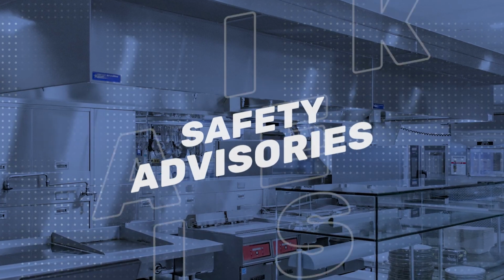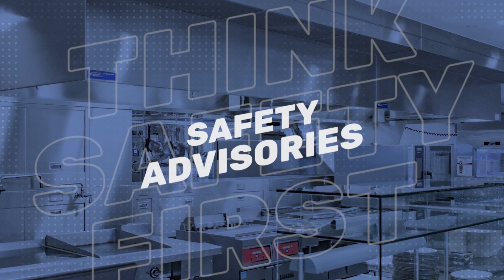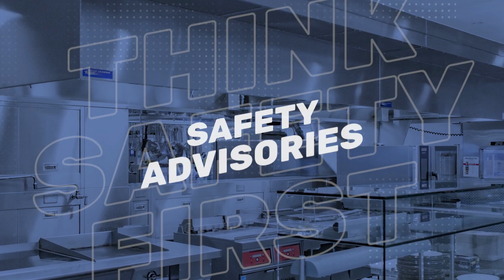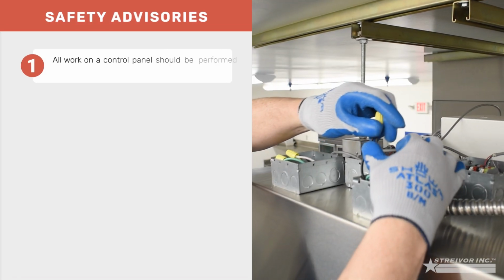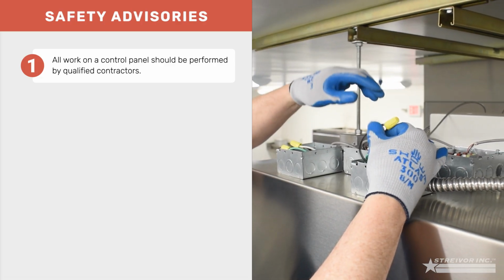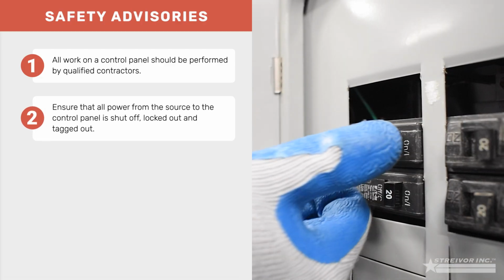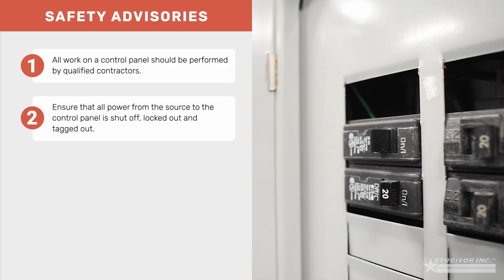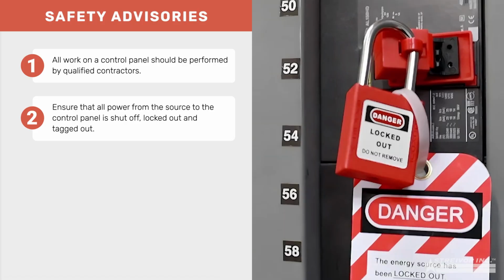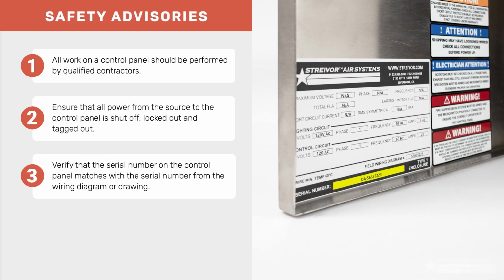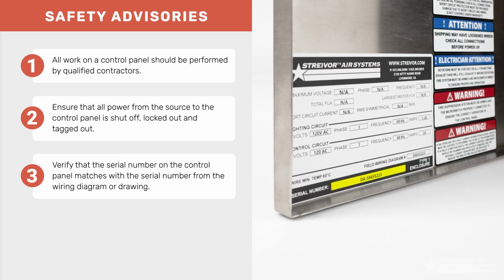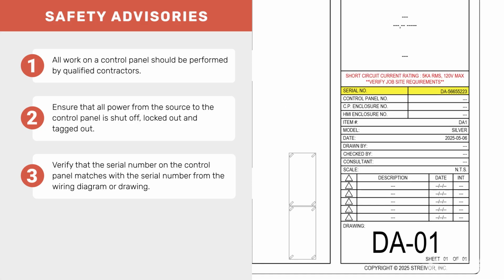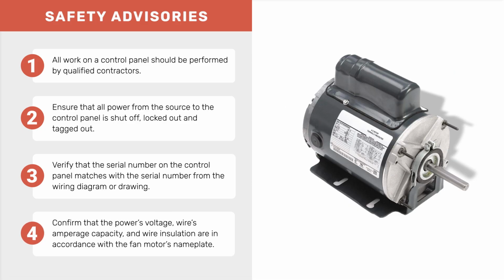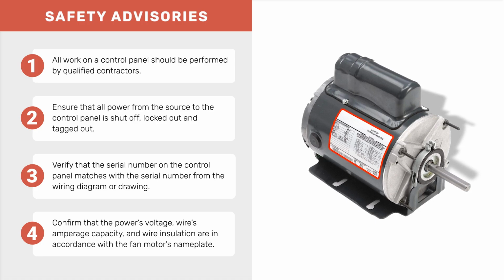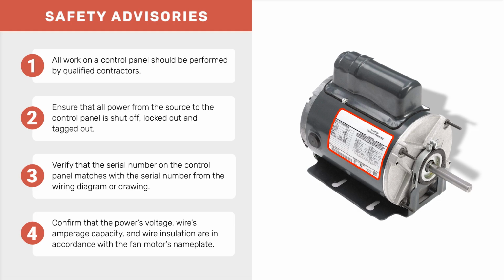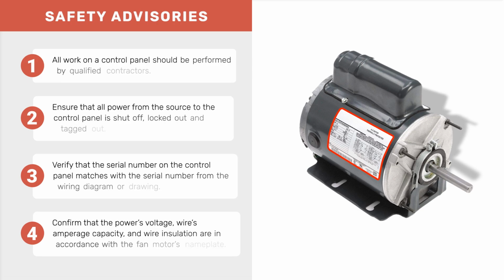Consider these safety advisories when performing tasks on a hood system and the DemandAire Gold Control Panel. Ensure all work is performed by qualified contractors. Ensure that all power from the source to the control panel is shut off, locked out, and tagged out. Verify that the serial number on the control panel matches the serial number from the wiring diagram or drawing. Confirm that the power's voltage, wire's amperage capacity, and wire insulation are in accordance with the fan motor's nameplate.